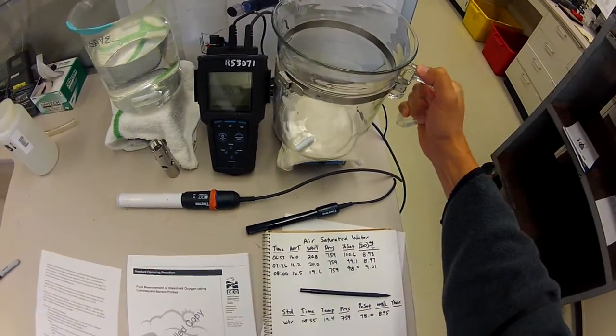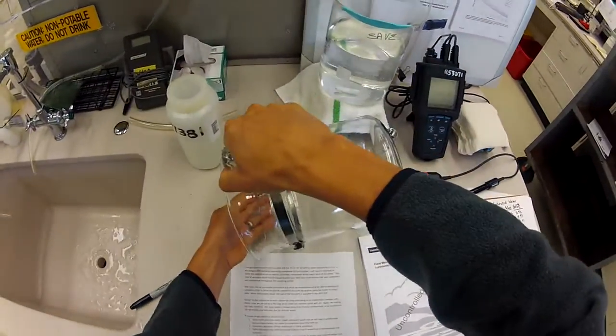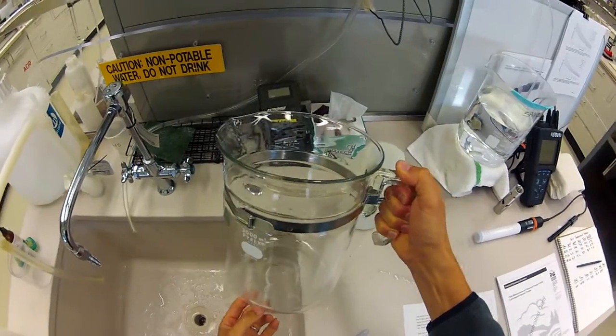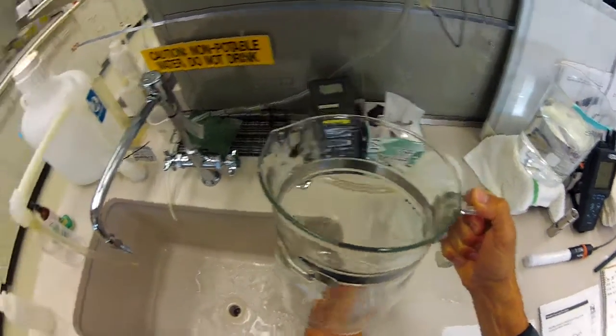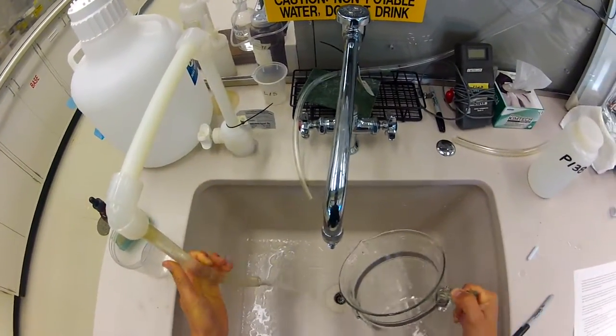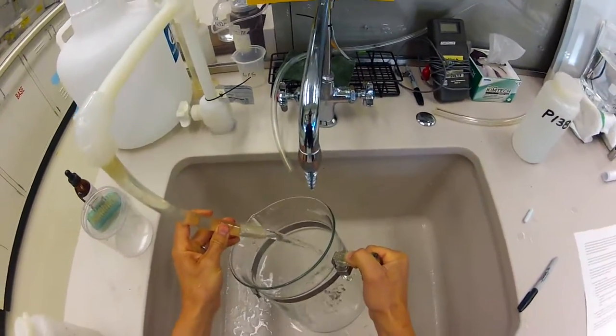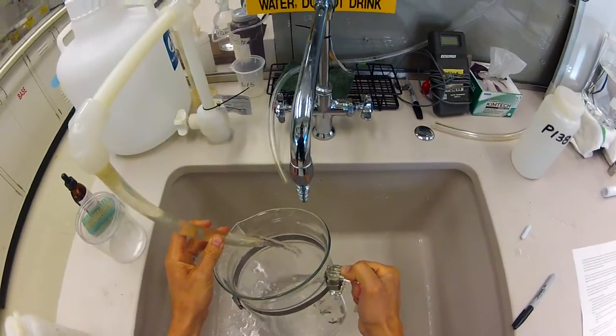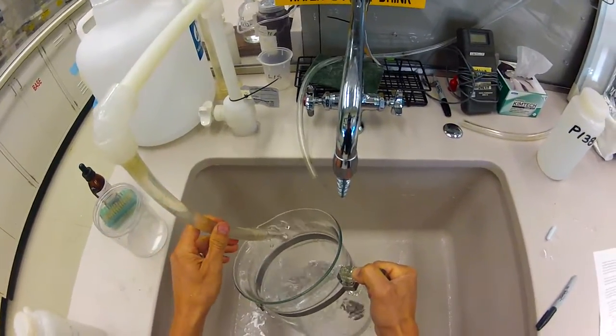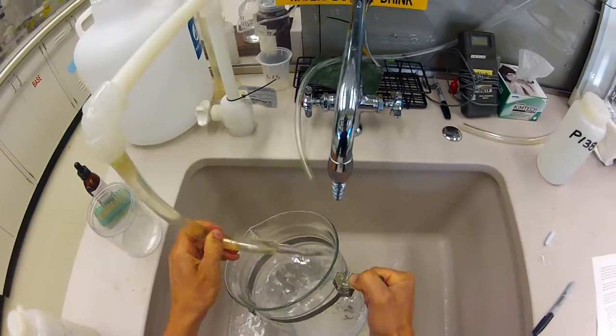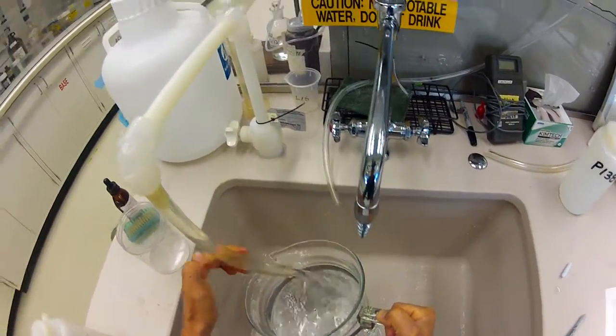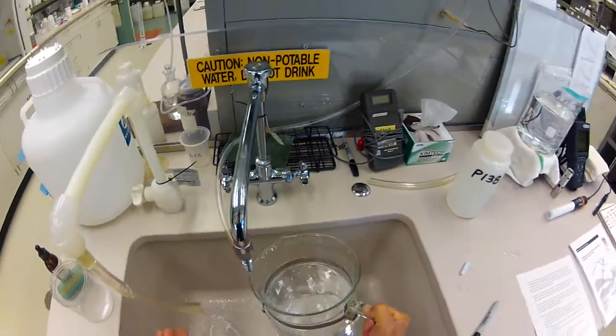Let's go ahead and show you how to make this standard. I've got a vessel here that I'm going to be able to put about one and a half liters of water in. I'm going to use water from this tap, which happens to be deionized water. I happen to know that the water coming out of this tap is going to be at right about 100% saturation and usually pretty near room temperature.